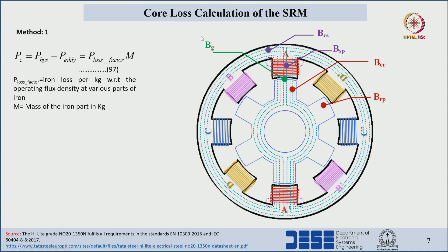For core loss calculations we follow method one as discussed in the case of the induction machine. The Steinmetz coefficients and frequency terms will not apply to the SRM — using them would give incorrect calculations. Instead, the power loss factor multiplied by mass is used. First, identify the maximum operating flux density points with respect to all regions.